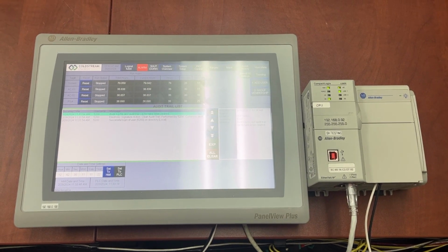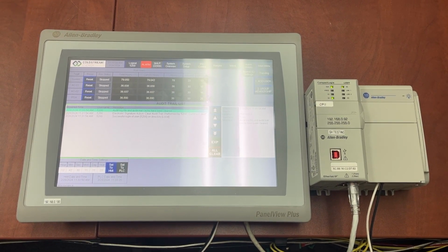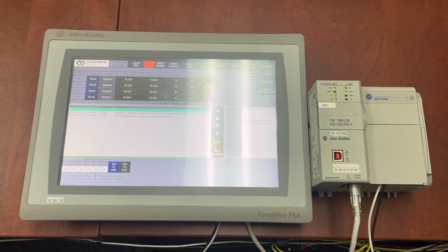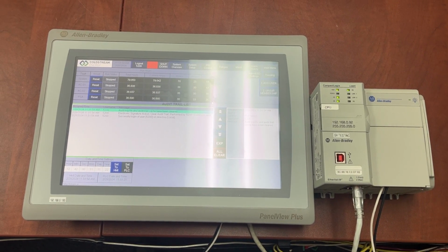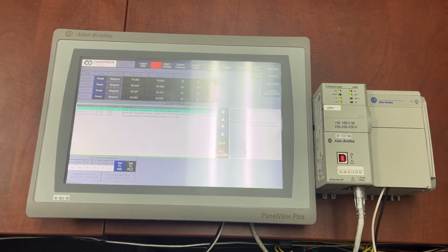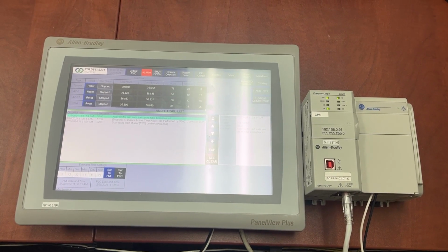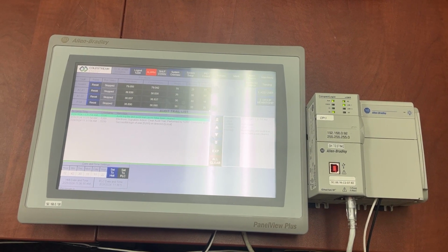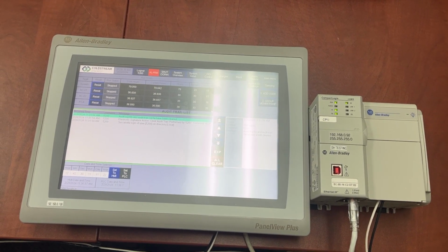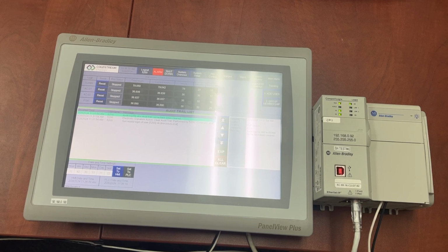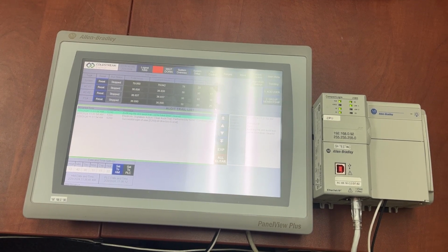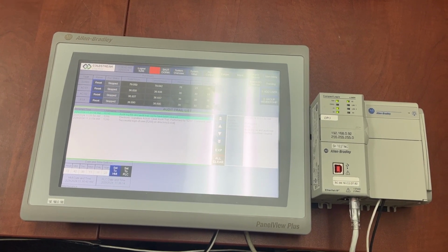The problem is that in those exported CSV files, the timestamps for alarm messages and HMI activities or events are in UTC zone only. If UTC time zone is not selected in the HMI configuration, those timestamps can be very different from the date and time shown on the HMI.